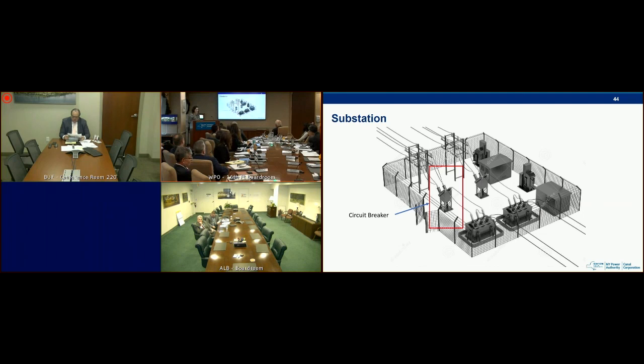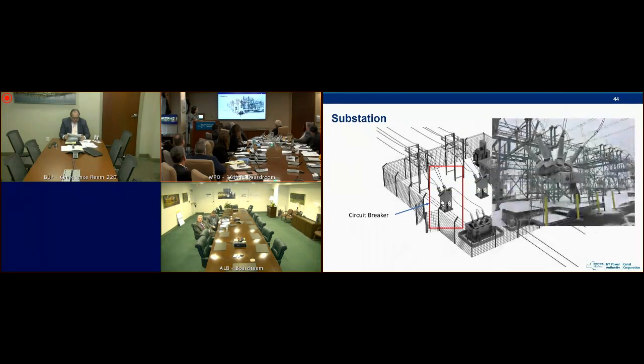The next component would be the circuit breaker. Circuit breakers are automatic devices that stop the flow of current in the electric circuit as a safety measure. The majority of breakers being replaced under the TLEM are original oil-filled circuit breakers, which we're replacing with gas-filled SF6 breakers. The new breakers are outfitted with additional monitoring tools and sensors, and here is a photo of a typical breaker on our system - this one, again, is up at Massena Sub. They're all taken the same day.